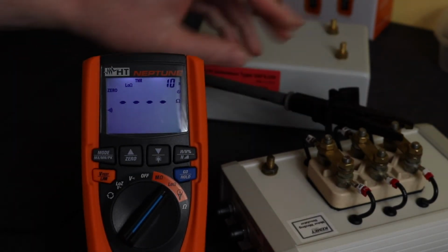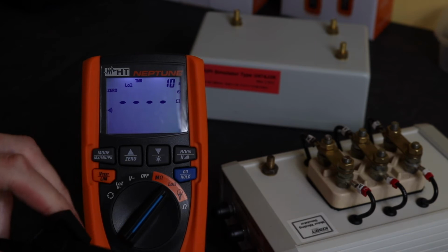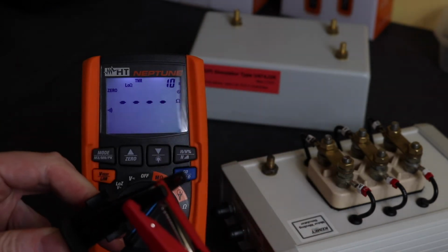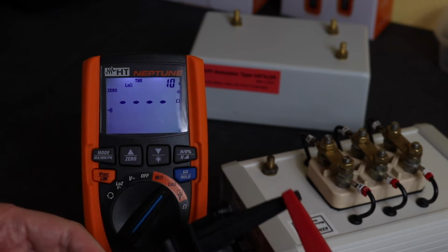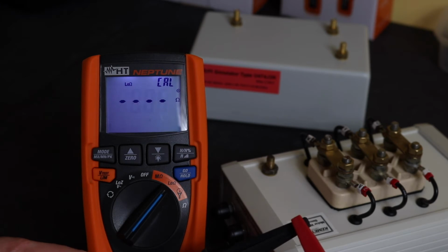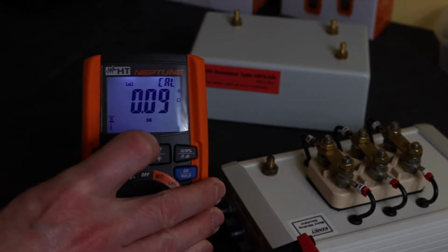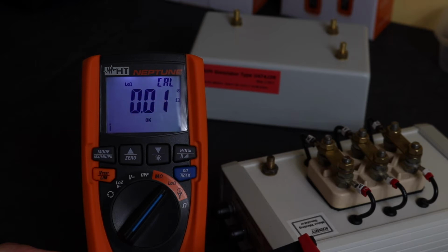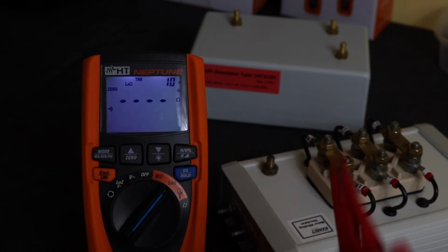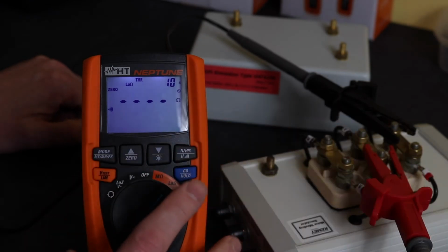Okay, so we'll use our winding simulator again. First of all, we need to zero it. So this has a zeroing function as well. I'll clip the leads together and hold the 0, and it goes through a little cal. 0.08, it's not bad. Interesting. Didn't zero that out completely, did it? 0.09, 0.01. Okay. Got the total 0. We'll see what readings we get with regard to this.